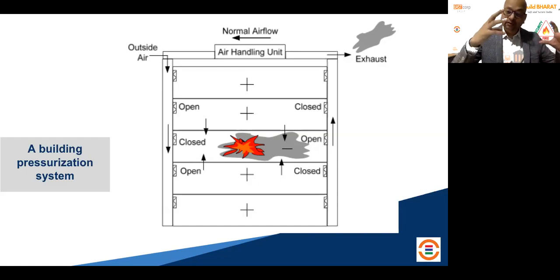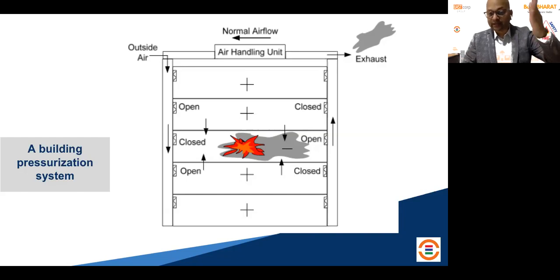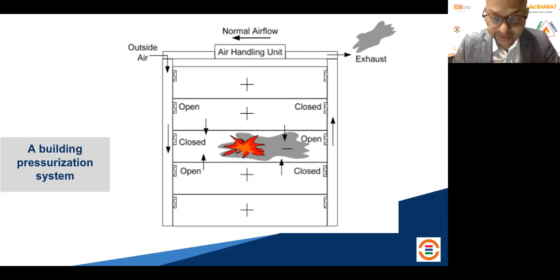You create what? A wall, or maybe a fire curtain. There are now ways allowed such as fire curtains, where you can have the desired rating from 1 hour to 3 hours, operated by the fire alarm, and you confine that smoke into that area, as given in the codes and standards. So if it is the car park, which is the basement area, NBC currently says that 3000 square meter is the confined area. If it is other than car park, 2000 square meter area.